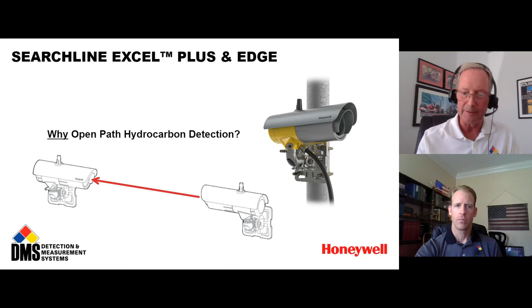But you'll also end up with a gas detection system that is cheaper to install, with fewer detectors to maintain. It'll bring down the overall cost of your gas detection system to utilize both point and open path in the traditional industrial applications that we run into. So open path hydrocarbon gas detection is a technology that should be very seriously considered by any company that has hydrocarbon gases that they need to detect.